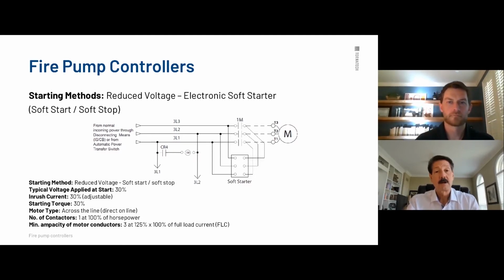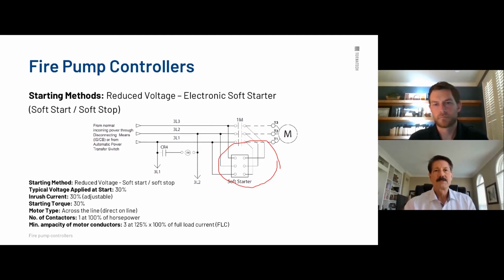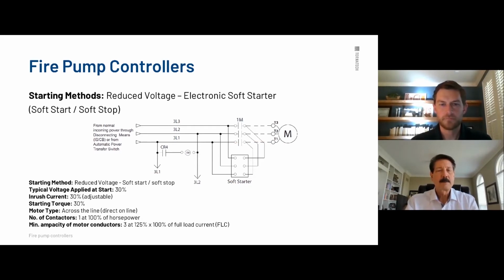Oh, soft start, here we are. This is that little black box I'm talking about. Again, don't get confused thinking a soft start is like a VFD, a variable frequency drive, because it is alike in that they're both electronic, but there are differences. So a soft start will allow you to ramp your motor up to a certain speed. Now, we all know on normal power by code, you need to have your motor up and running in 10 seconds or less. That's the maximum amount by code.